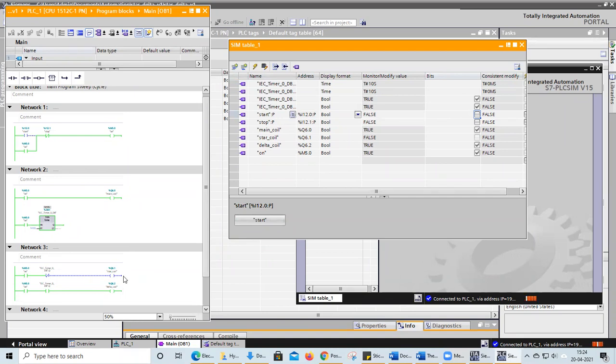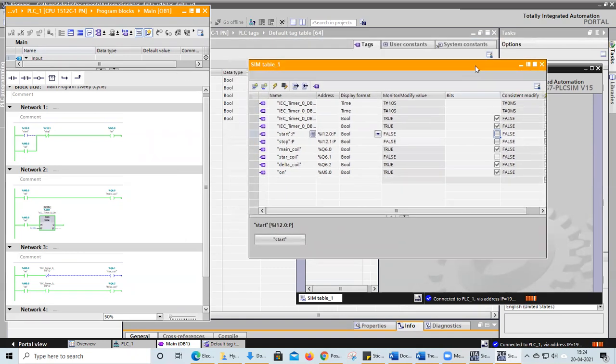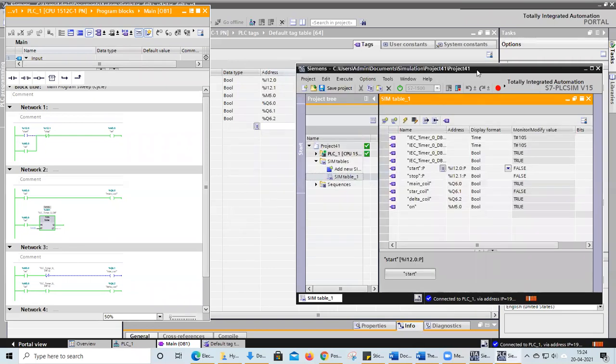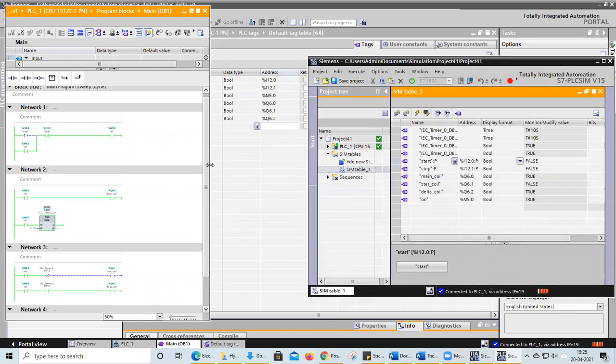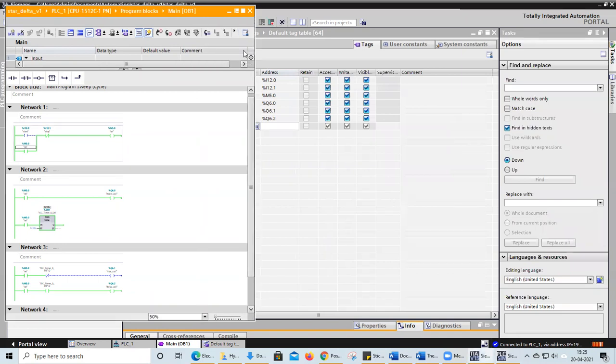Yesterday, this did not happen because we had given the time period in microseconds. So we were unable to see with our eyes when the switchover had taken place. So I have increased the time period. Now it is working fine. Now you can see it clearly also. Our circuit is switched from star to delta here. Does anyone have any doubts in star delta conversion?